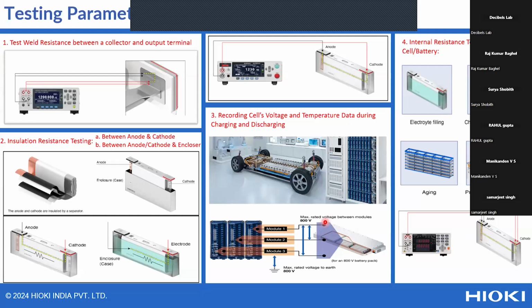After that, the second parameter is insulation resistance. We need to check the insulation resistance between anode and cathode, and between the electrode and the enclosure of the battery. It must be as high as possible, because if it is low, there is a chance of a short circuit, due to which there is a chance of fire hazard.